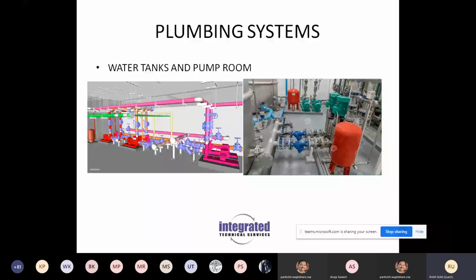On the right-hand side, you can see an image of the pumping systems. Now, these pumps and this brown color device over here, this is called an air vessel. These pumps are part of a system called a hydro-pneumatic system. Hydro is water, pneumatic is air. A hydro-pneumatic system supplies water directly from the underground tank directly into each of the bathrooms and to the terminal devices like taps or sinks or showers or whatever the water is being used for. It doesn't get pumped into an overhead tank and come by gravity. As the pipes go up, they keep tapping into all the floors.